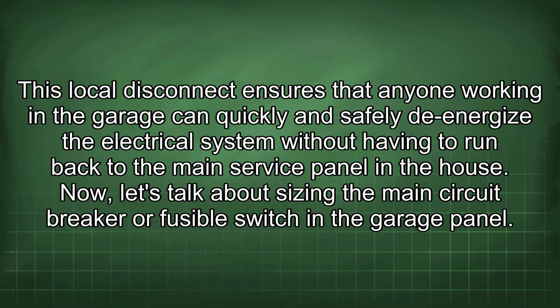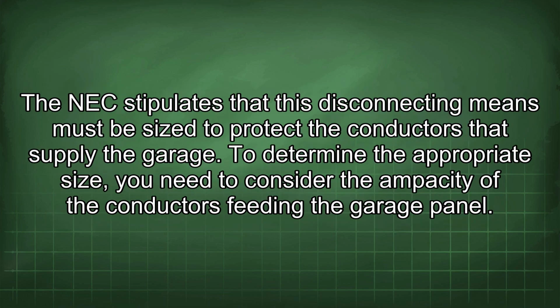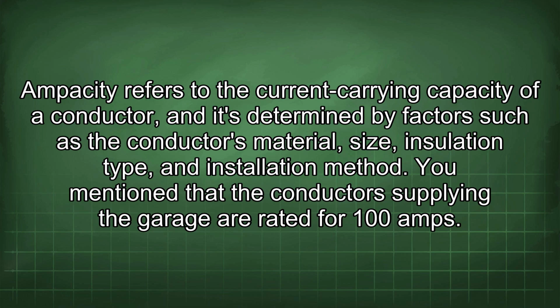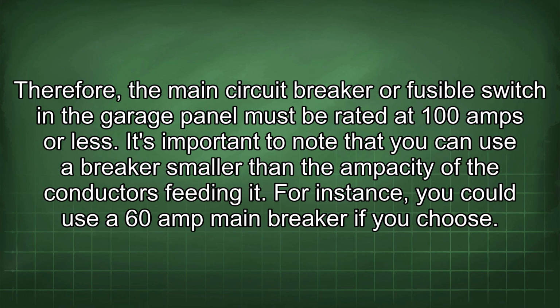Now, let's talk about sizing the main circuit breaker or fusible switch in the garage panel. The NEC stipulates that this disconnecting means must be sized to protect the conductors that supply the garage. To determine the appropriate size, you need to consider the ampacity of the conductors feeding the garage panel. Ampacity refers to the current carrying capacity of a conductor, and it's determined by factors such as the conductor's material, size, insulation type, and installation method. You mentioned that the conductors supplying the garage are rated for 100 amps. Therefore, the main circuit breaker or fusible switch in the garage panel must be rated at 100 amps or less.